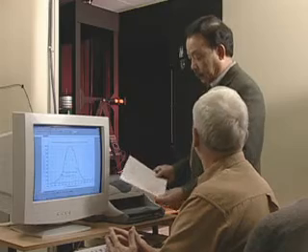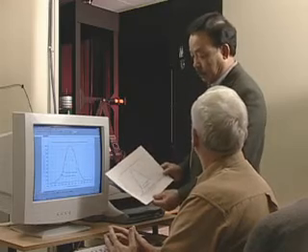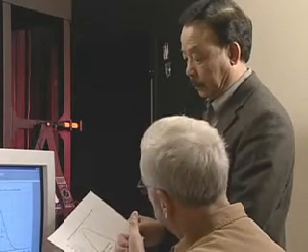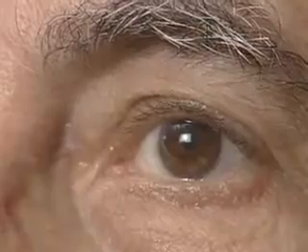Calibration against the CIE response curve permits precise determination of spectral correction factors for a light of any color. The control computer is programmed to scan either the horizontal or vertical axis, recording an intensity measurement for each angle setting. The result is the average human eye's response to the viewing of that light.